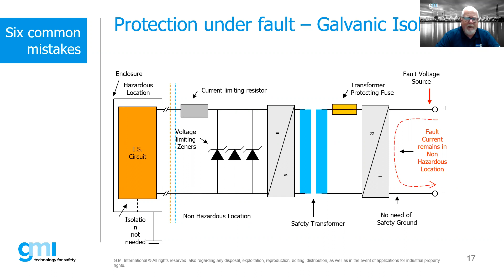Now, the other type of barrier that you will find, associated apparatus, is what is called a Zener barrier. A Zener barrier also has a current limiting resistor, we have a fuse, and we also have voltage limiting Zener diodes. But what we don't have is a safety transformer located within the barrier itself. Now, under a normal fault condition, if we have a fault and the current starts flowing, if it gets above a threshold for the Zener diodes based upon the voltage, they will open up. So if we have a high voltage spike, it'll open up and it should allow all that excess voltage to go to ground.